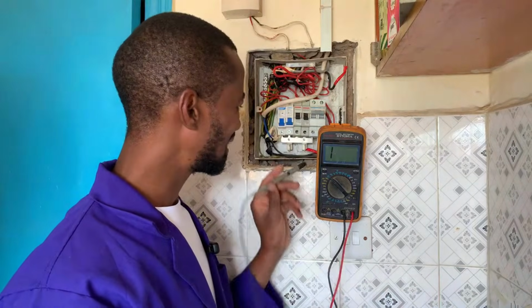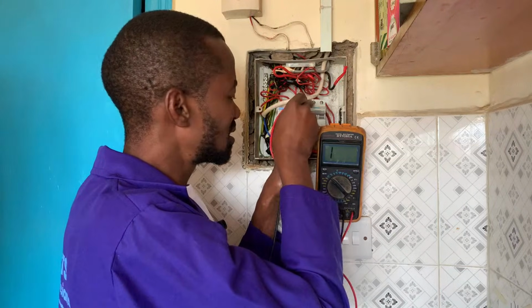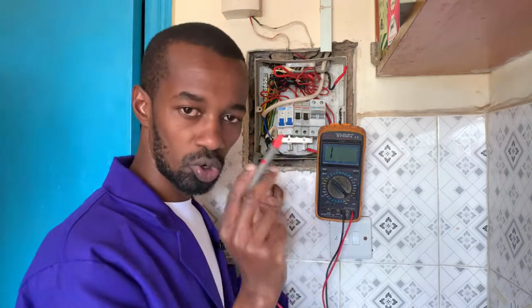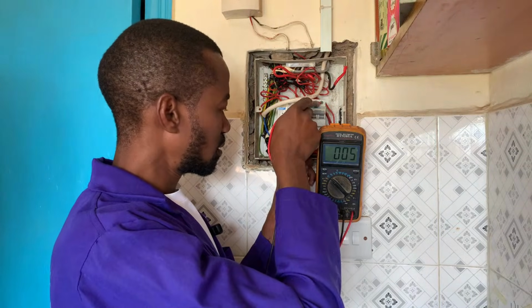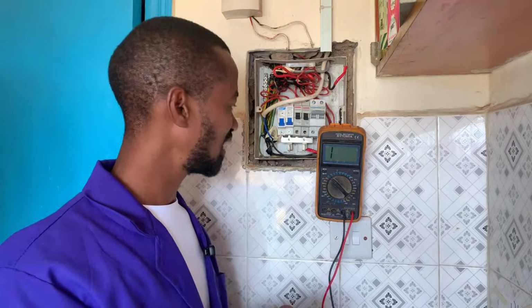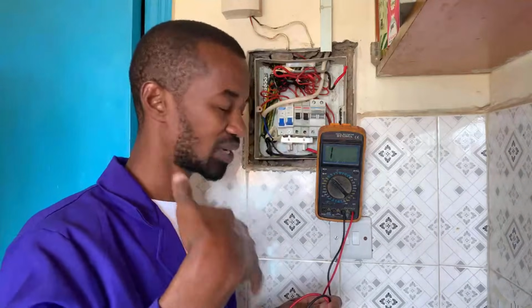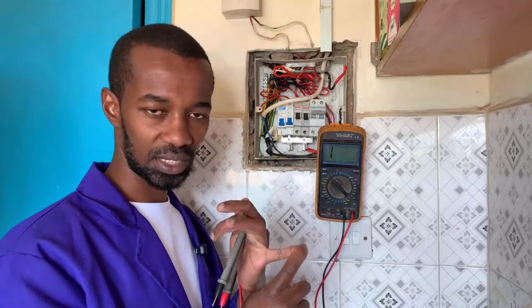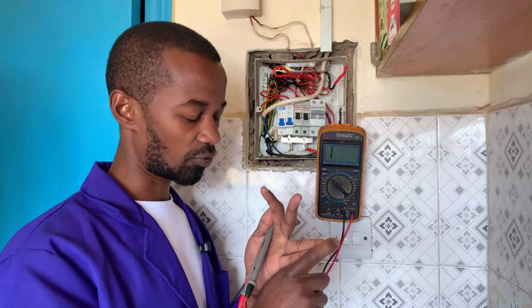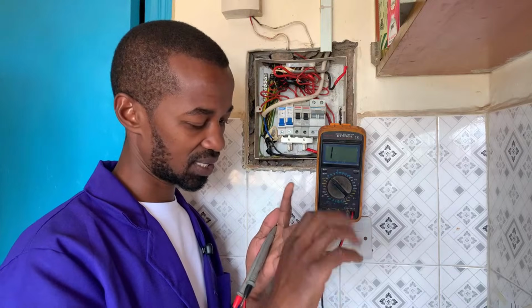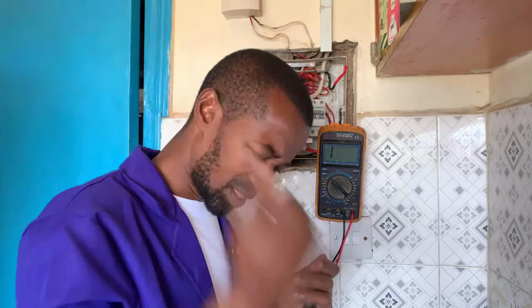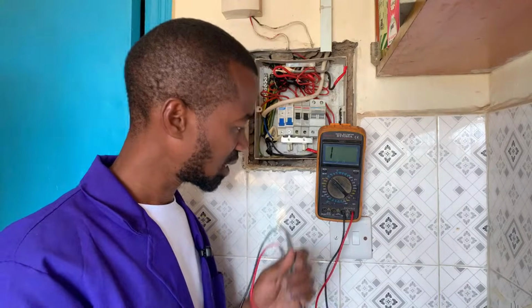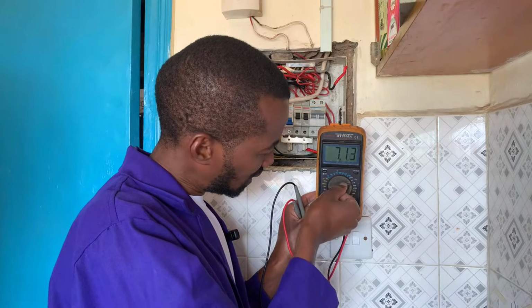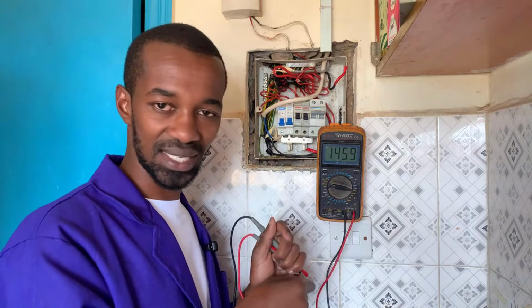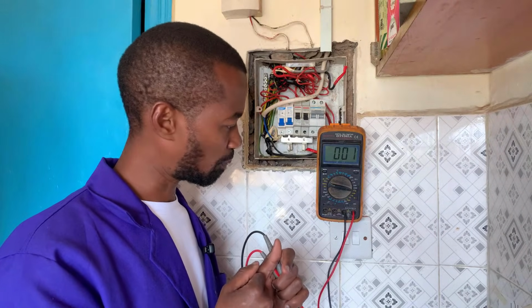Apart from testing that, another issue I would like to highlight is that whenever you carry out the test and find that everything seems okay when no load is connected, you need to go ahead and test for the voltage output at the point where all the loads are already connected - assuming there's a washing machine, the lighting circuit, the sockets, and all that. Ensure that everything in that house is powered on, and then come and perform another important test here, referred to as AC output, my top bosses.